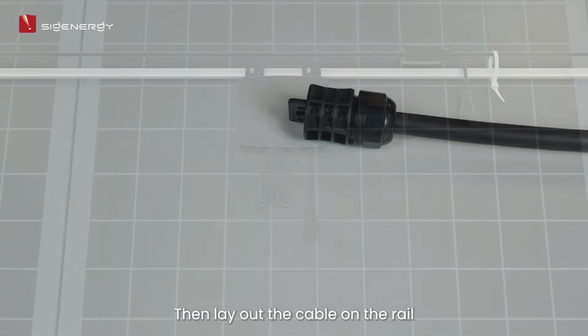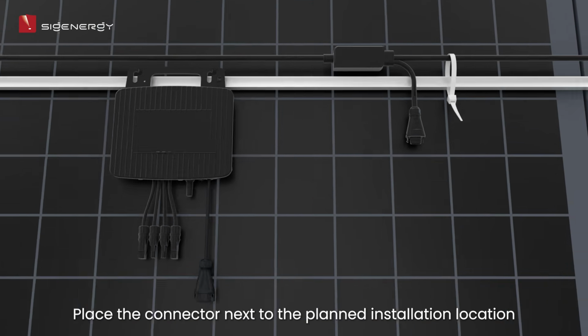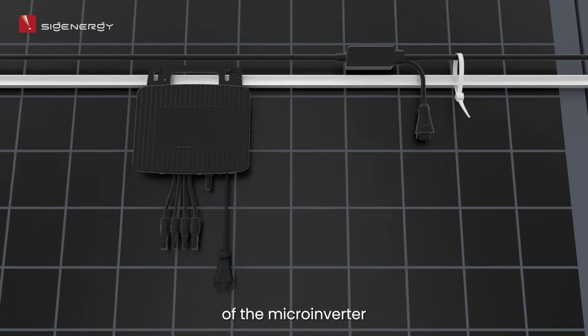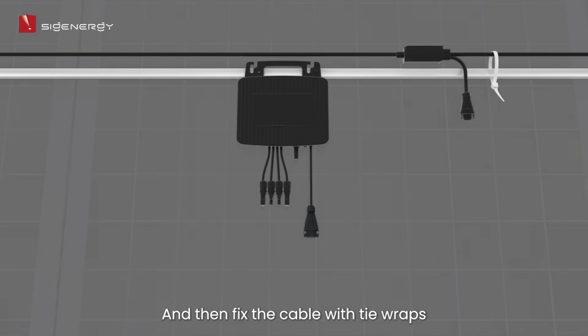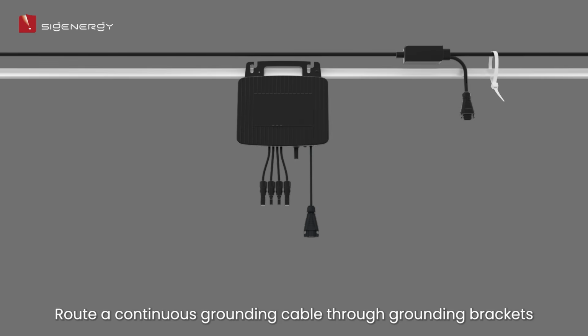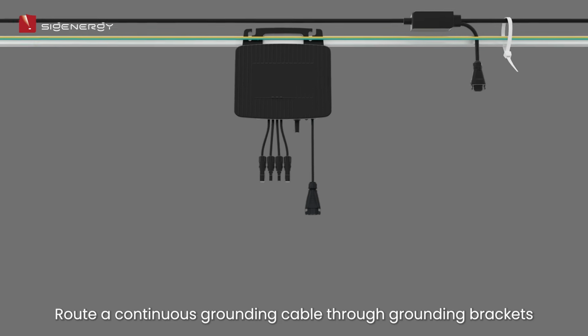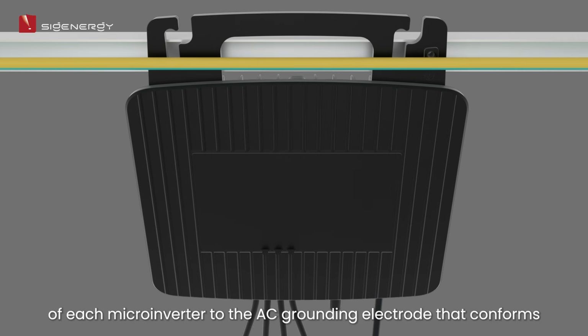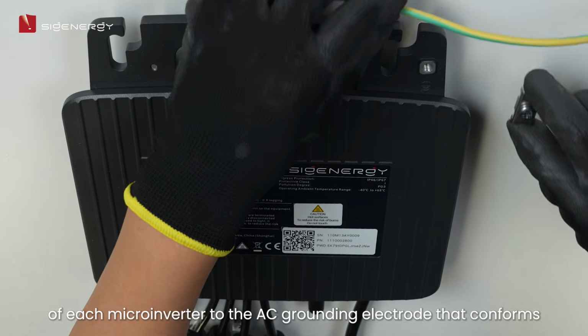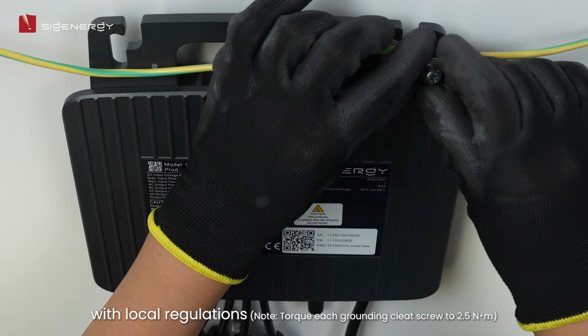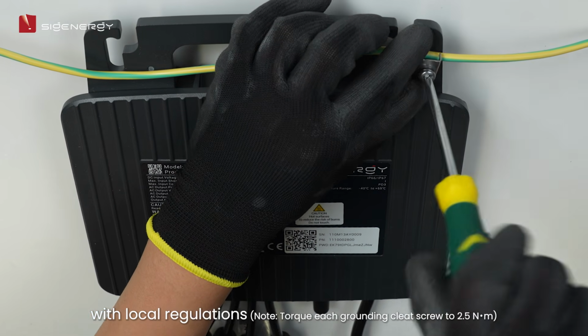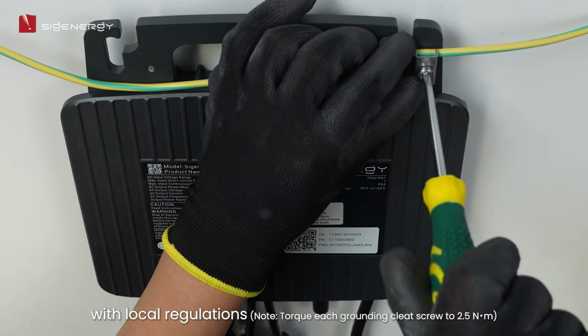Then lay out the cable on the rail. Place the connector next to the planned installation location of the microinverter, and then fix the cable with tie wraps. Route a continuous grounding cable through grounding brackets of each microinverter to the AC grounding electrode that conforms with local regulations. Note, torque each grounding cleat screw to 2.5 Newton meters.